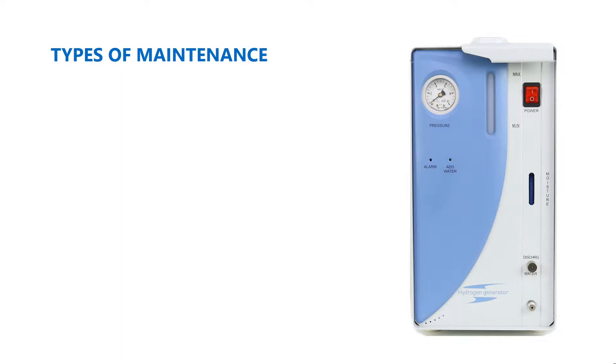Types of maintenance: Current and Periodic. Current Maintenance includes generator purity monitoring, hydrogen pressure monitoring, hydrogen water content monitoring, and water level monitoring. All monitoring operations are to be performed daily.